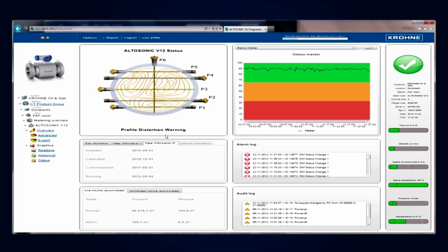This meter is running okay, but there are some flow profile distortion issues. As you saw in the picture, this meter is running on atmospheric air. There is no inlet and outlet. So once in a while, we might see the flow profile is slightly distorted. This is the start screen.